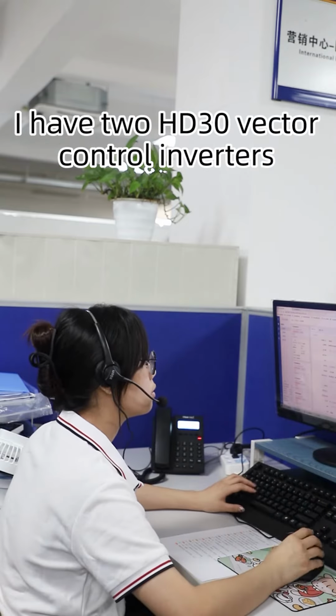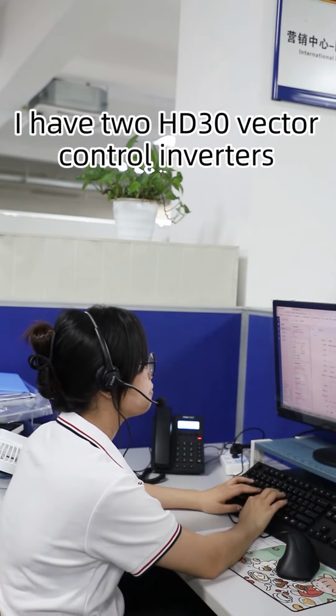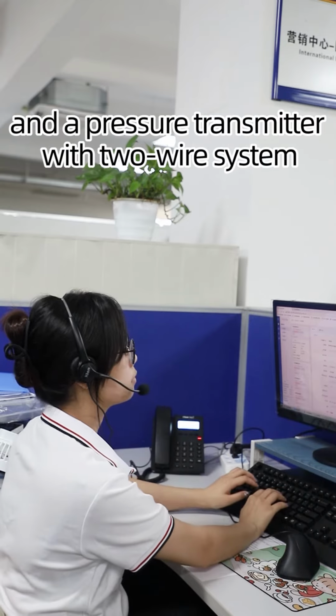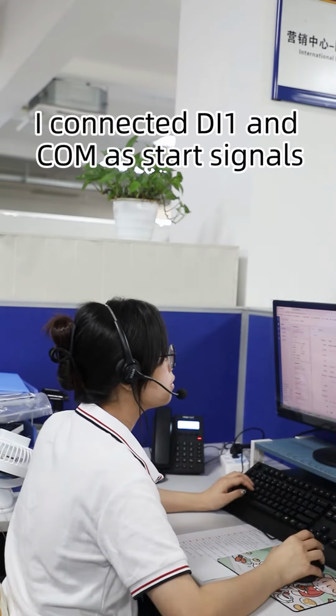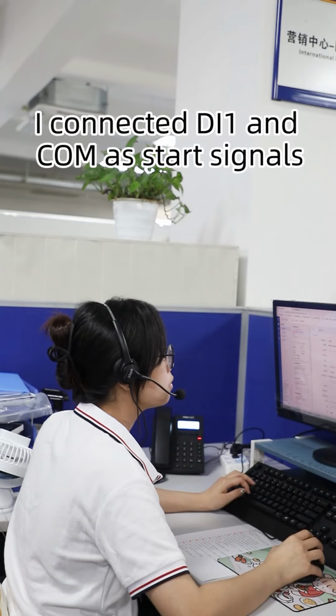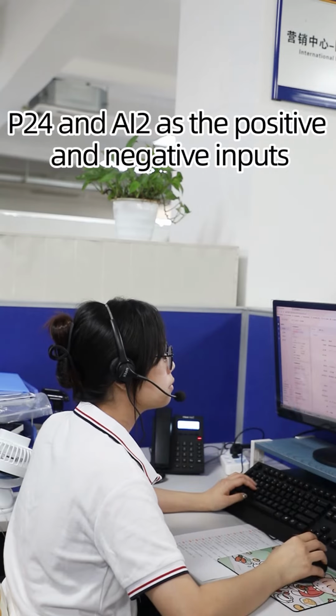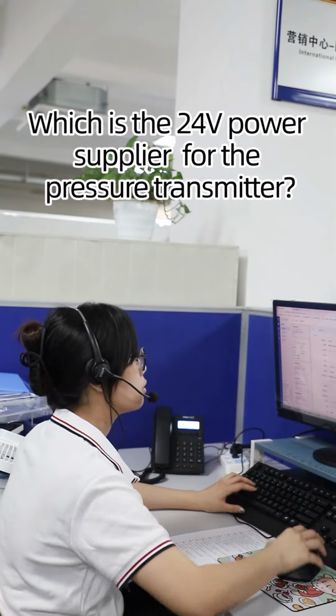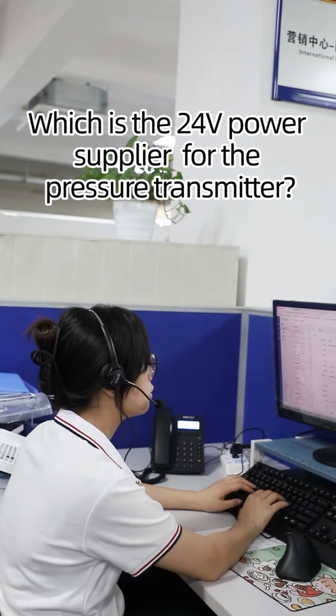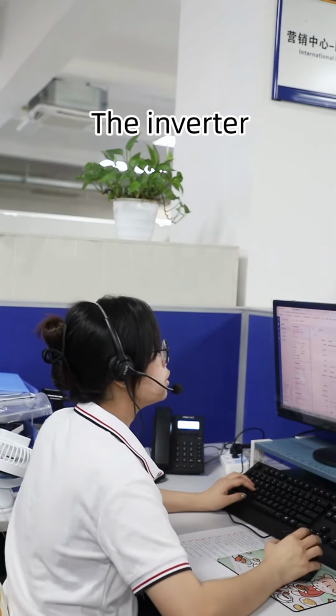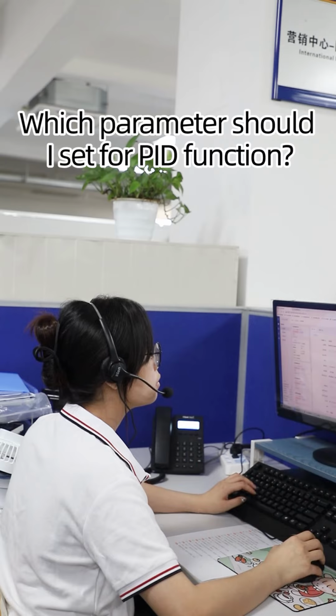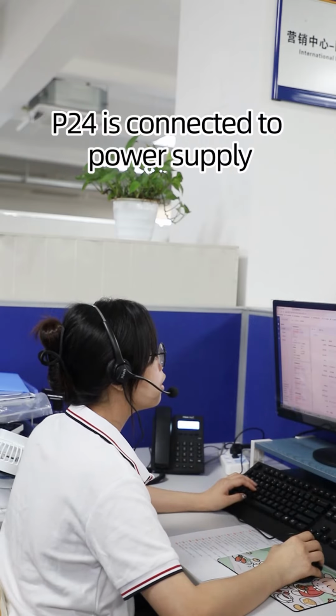I have two HD30 vector control inverters and a pressure transmitter with a two-wire system. I connected DI1 and COM as start signals, P24 and AI2 as the positive and negative inputs. Which is the 24 volt power supply for the pressure transmitter? The inverter. Which parameter should I set for the PID function?